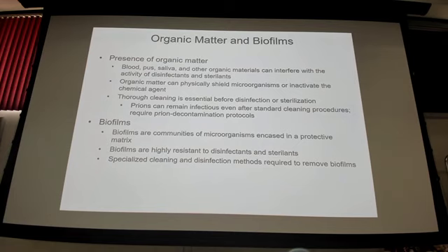Okay. Organic matter and biofilms, another important factor in determining efficacy. Going back to surgical equipment, that has to be reused because it's really expensive. If you put scissors or a scalpel straight out of surgery into an autoclave with gross organic material visibly on it, is that autoclave going to get rid of that organic material? No, it's not. It doesn't have sprayers inside the autoclave or anything like that. All it's going to do is cook that material onto the surgical instrument.